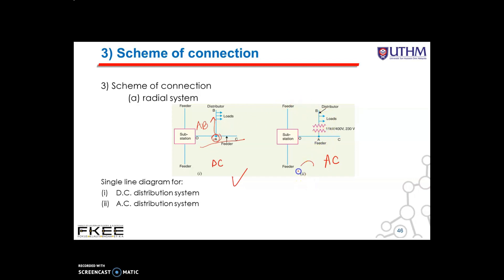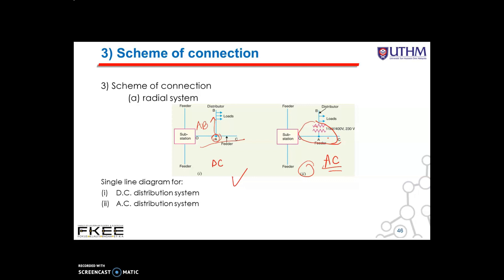Figure 2 shows a single line diagram of a radial system for AC distribution. The radial system is employed only when power is generated at low voltage and the substation is located at the center of the load. This is the simplest distribution circuit and has the lowest initial cost. However, it suffers from the following drawbacks: the end of the distributor nearest to the feeding point will be heavily loaded.